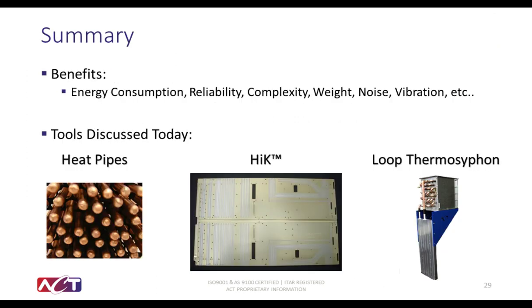At this point, we've talked about heat pipes, high-K technology, and loop thermosiphons, all of which are passive or semi-passive advanced solutions for heat transport in your systems. The benefit of passive thermal operation can be in energy consumption, increased reliability, decreased complexity and weight, and reduction of noise and vibration which may be caused by pumps and fans.